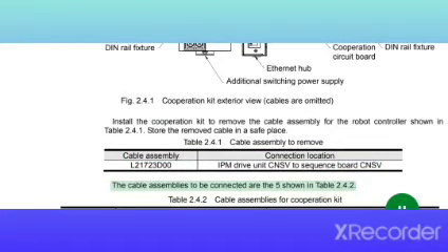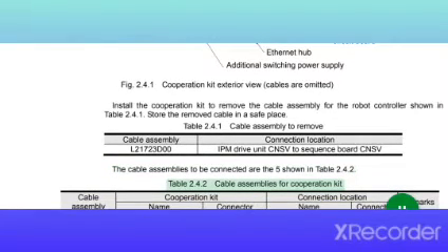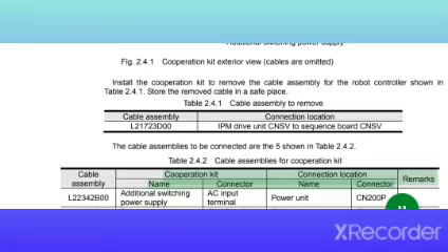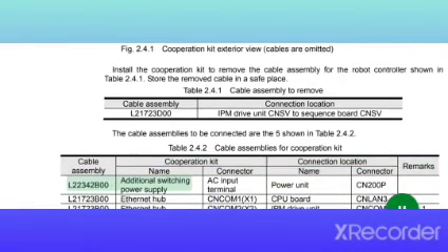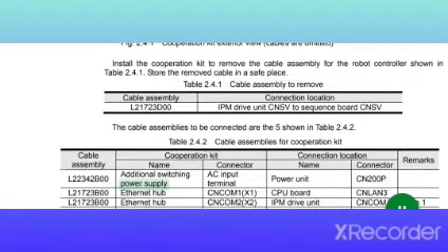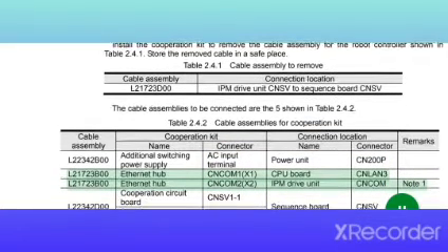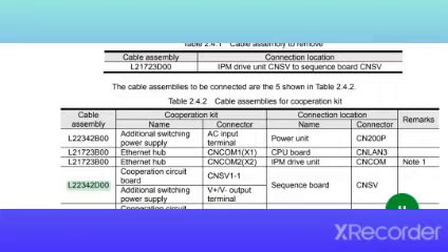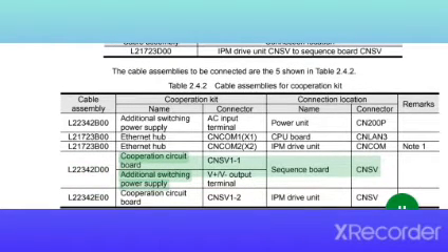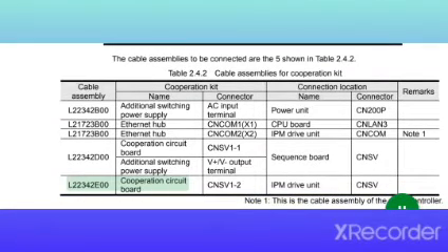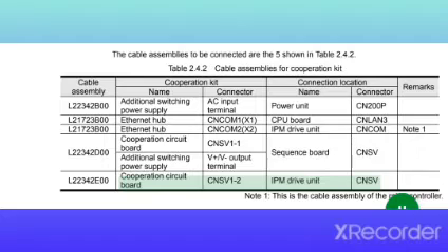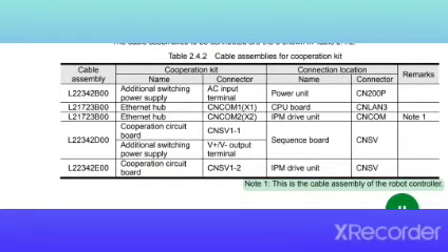The cable assemblies to be connected are the 5 shown in Table 2.4.2. Table 2.4.2 Cable assemblies for cooperation kit. Cable assembly name, cooperation kit connector, connection location, remarks. L22342B00 additional switching power supply, AC input terminal, power unit CN200P. L21723B00 Ethernet hub CNCOM 1X1, CPU board CNLAN 3. L21723B00 Ethernet hub CNCOM 2X2, IPM drive unit CNCOM Note 1. L22342D00 cooperation circuit board CNSV1-1, sequence board CNSV, additional switching power supply, +/- output terminal. L22342E00 cooperation circuit board CNSV1-2, IPM drive unit CNSV. Note 1. This is the cable assembly of the robot controller.